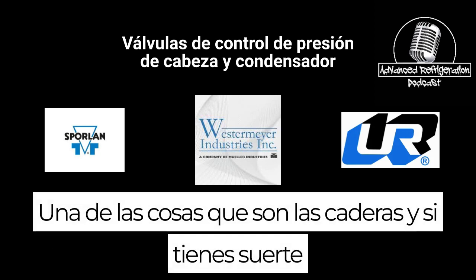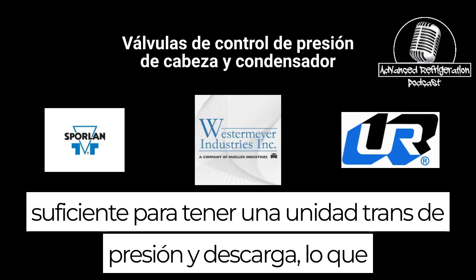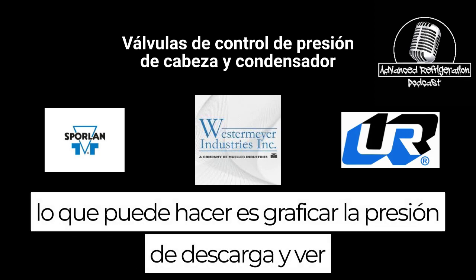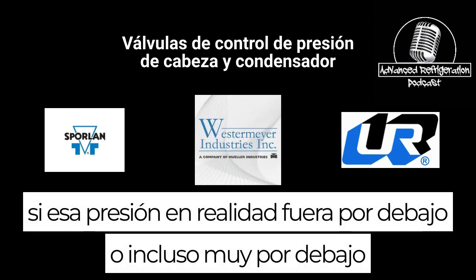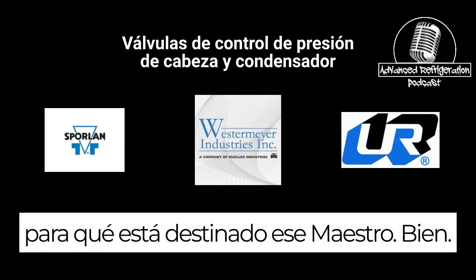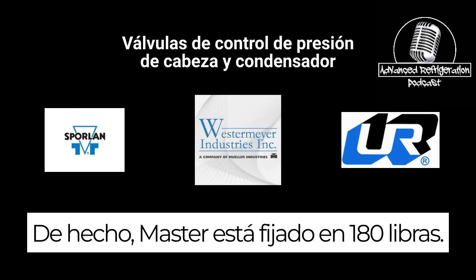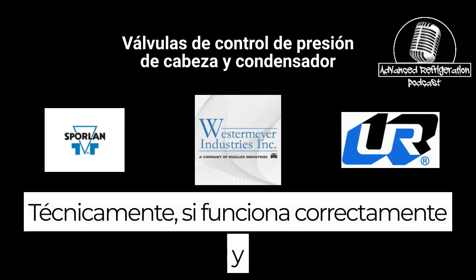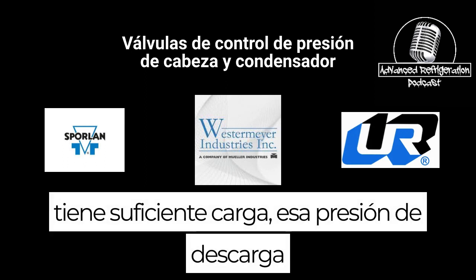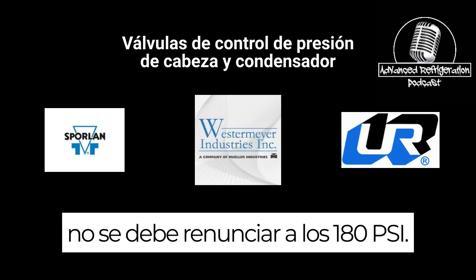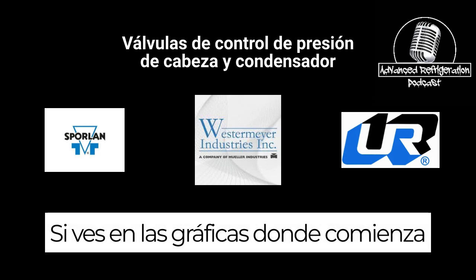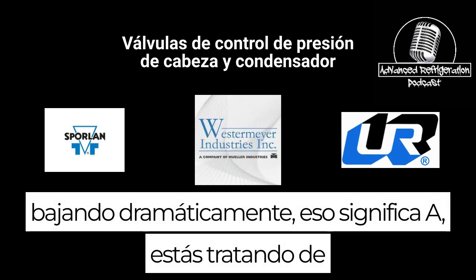One of the things, if you're fortunate enough to have a discharge pressure transducer, what you can do is graph the discharge pressure and see if that pressure actually went below, or even well below, what that headmaster is set for. I mean, headmaster is in fact set for 180 pounds. Technically, if it's working properly and it has enough charge in it, that discharge pressure should not waver from the 180 PSI.